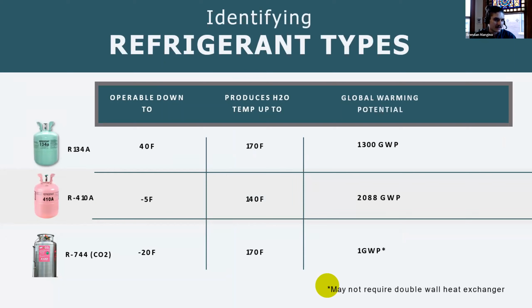Another negative with R134A is that they're not great for cold climates. They can only operate at an ambient temperature of 40 degrees Fahrenheit. Anything below that and they won't work. So usually in the climates we're designing in, we only use these for split systems or cascade systems, where this would be the indoor unit, or if you're using a water-to-water system.